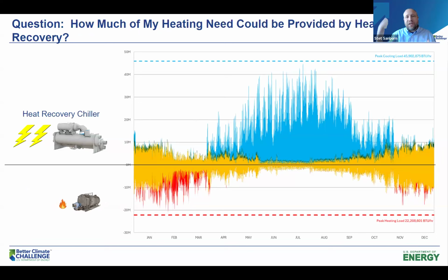And this is going to depend on what temperature regimes your buildings are at, but there are more and more products now coming onto the market that can do higher lift temperatures, 160, 165, even 180 in a couple of products that are on the market now, where you can take your chiller and instead of rejecting heat to the cooling tower, you actually reject that heat into your heating loop.